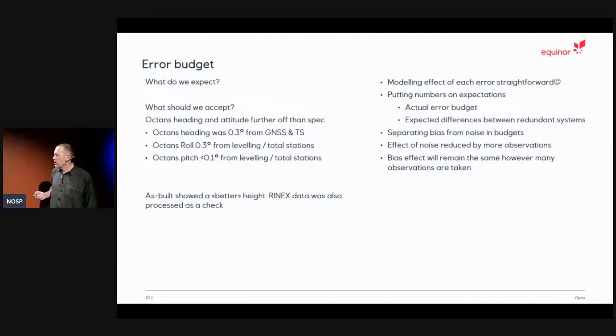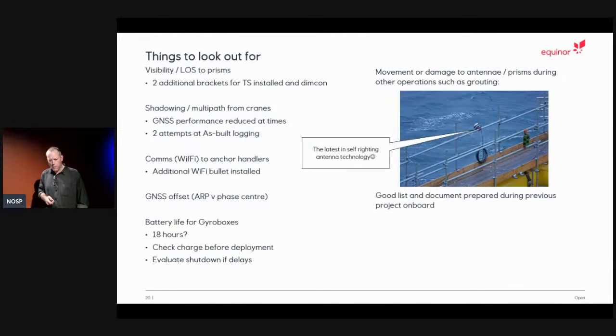It's quite important that we're able to spot bias from noise. So is it an error, a small residual systematic error, or is it just random noise? The effect of noise will be reduced by more observations, but the bias won't be. That should be quite simple to remember, but it's often forgotten. So a few things to look out for.